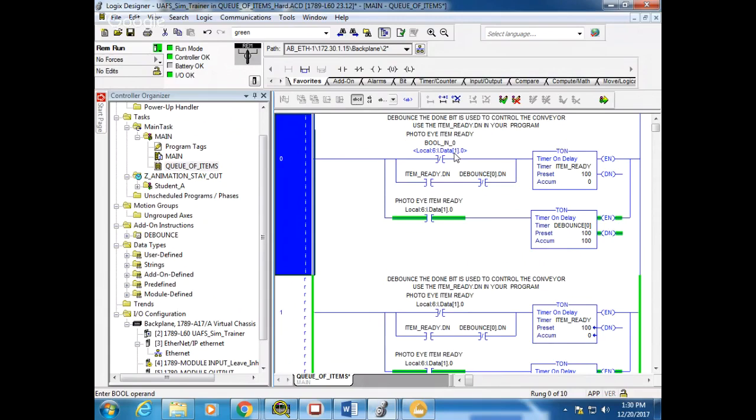So they're saying they're linked. If one comes on, the other one comes on, and vice versa. They are linked. And so you'll see that BOOL_IN_0 is the tag I'm programming, but it's actually an alias for this actual input. Are you with me? So that's how alias tags work. So if you start seeing that stuff with little addresses underneath like that, problem is I can alias an alias of an alias, if I so choose. And so I can have multiple tags that are all linked together and they're aliases for something else.